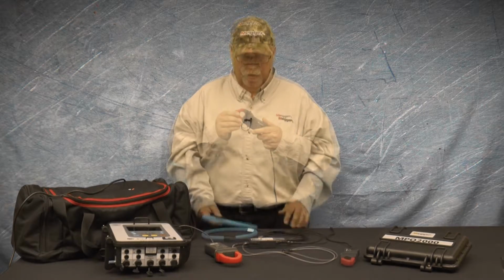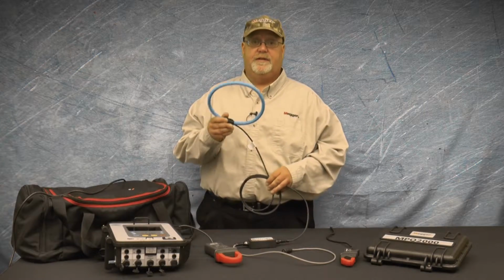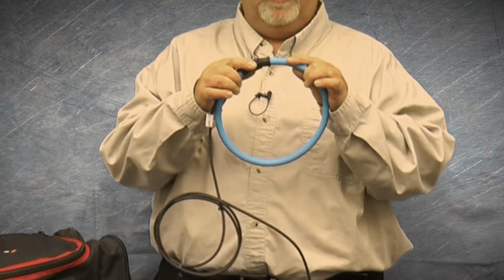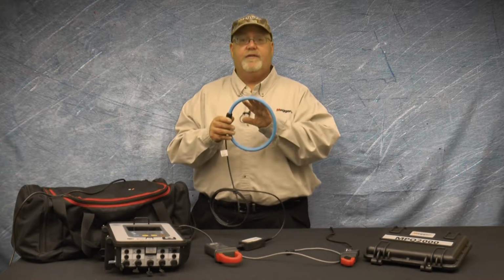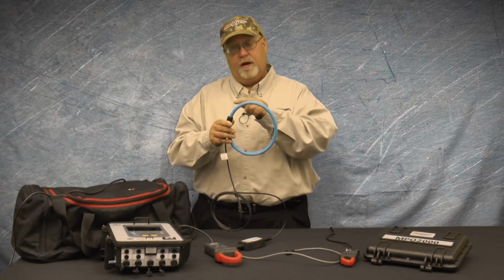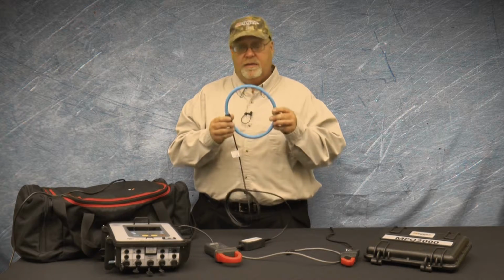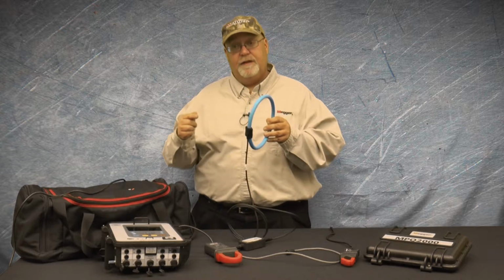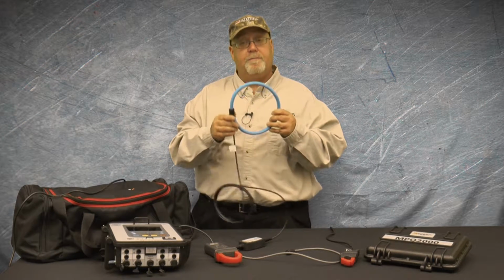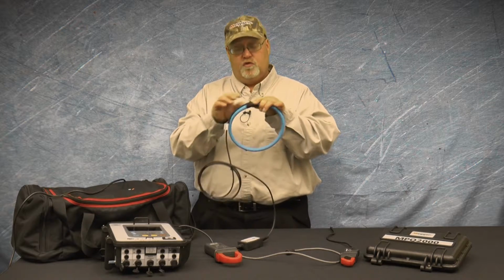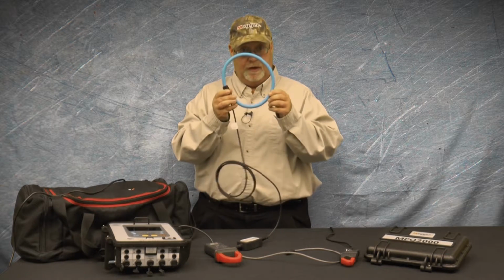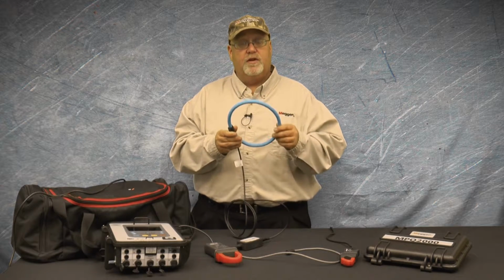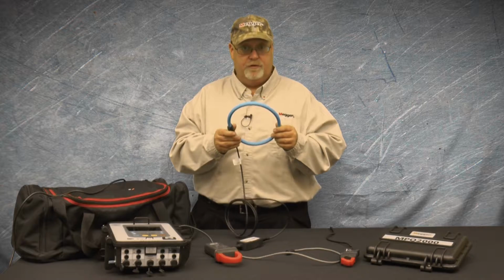The Rogowski coil, or flexible CT, is capable of being mounted around much larger cables and bus bars. The Rogowski coil current clamp consists of a wire wound around an air core. These are low permeability current clamps. The magnetic field produced by the conductor that this is measuring induces a voltage across the current clamp. This voltage has to be integrated over time in order to accurately represent the current being measured.